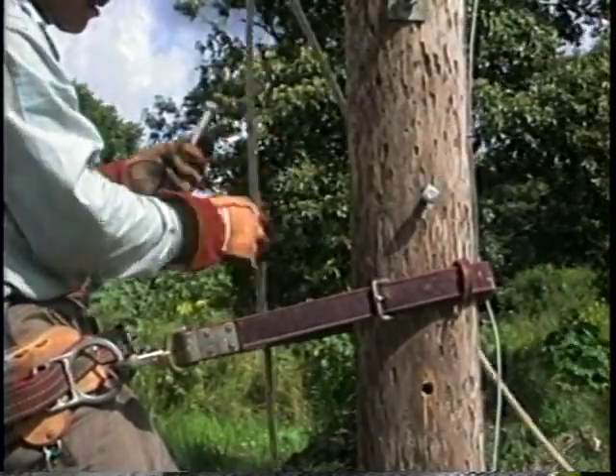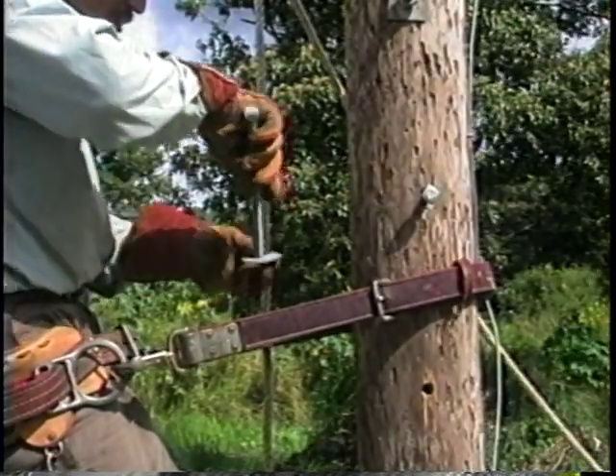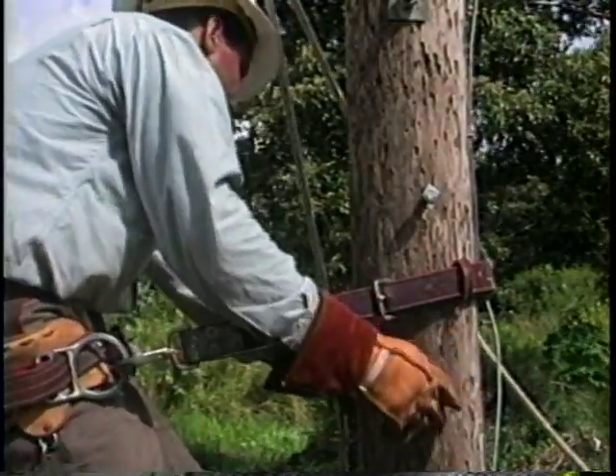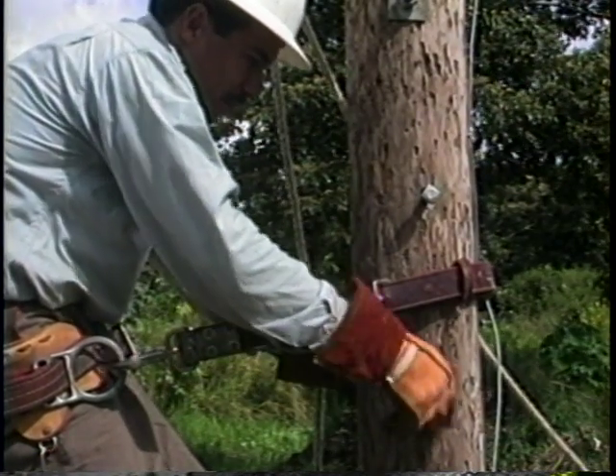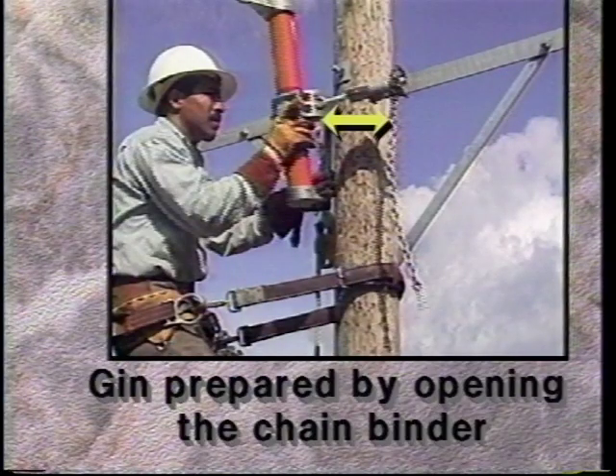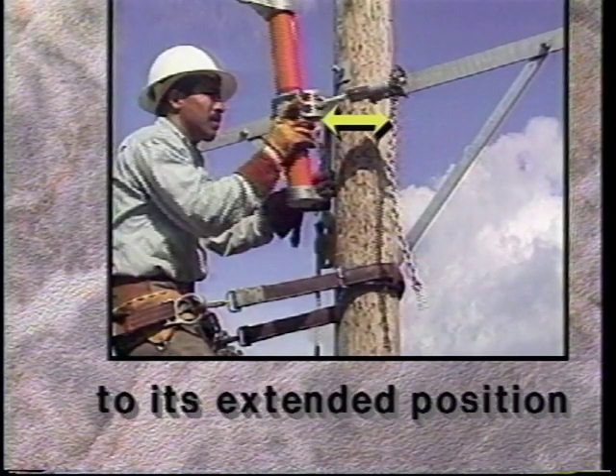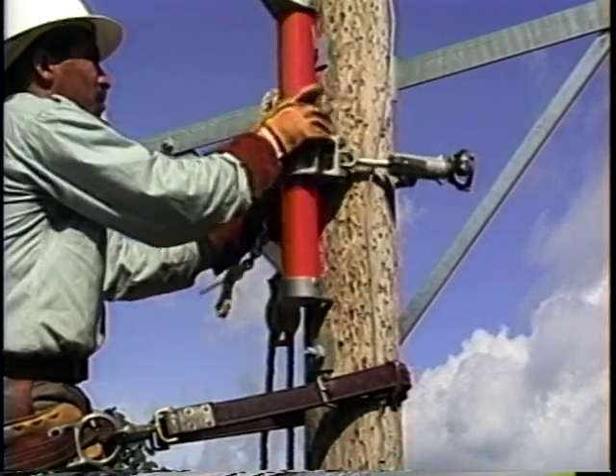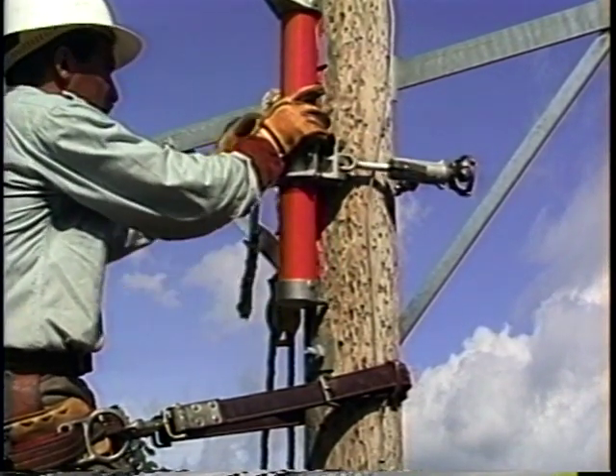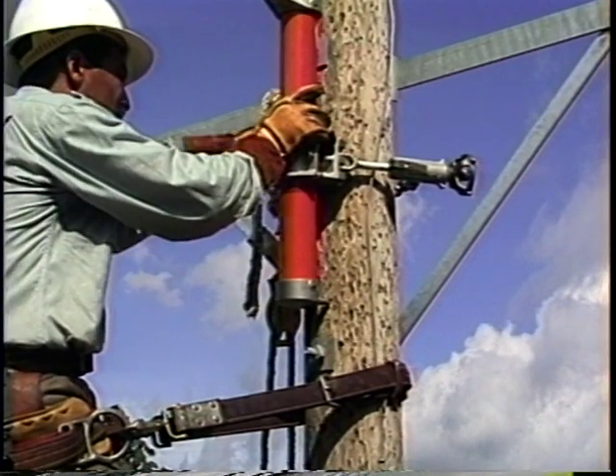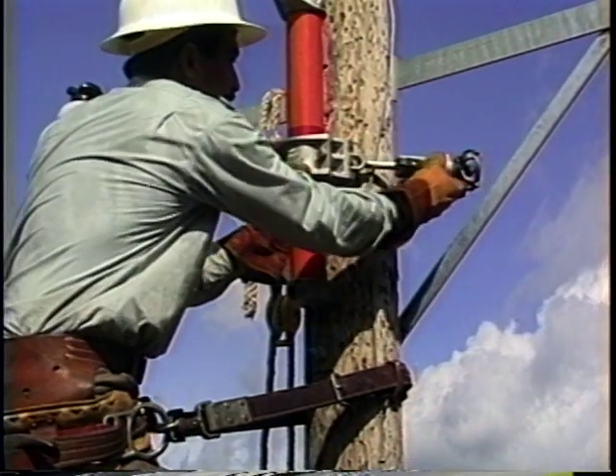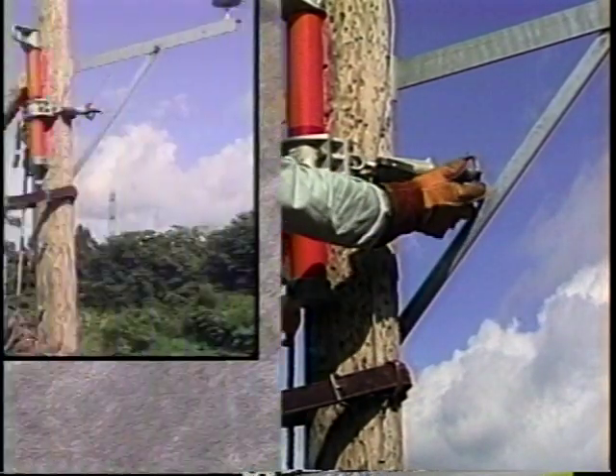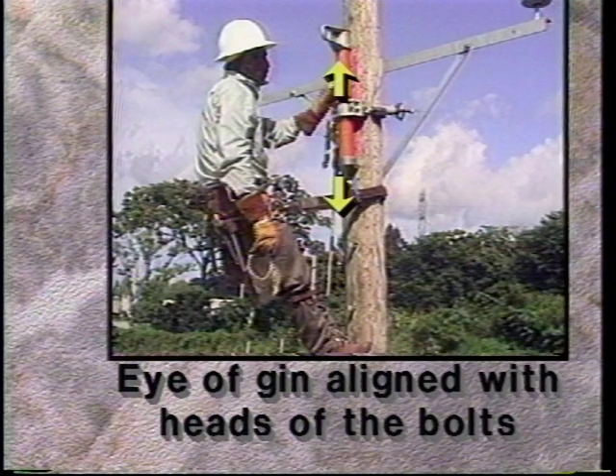Structure preparation. The position where the transformer will be is located, and holes are drilled if required. Machine bolts are inserted, with the heads placed on the side of the pole where the transformer hanger brackets will be located. The transformer gin is prepared by opening the chain binder to its extended position and then raised to the lineman. Once received, the transformer gin is installed. It should be positioned high enough on the pole to allow the transformer to be raised with the block and tackle. The eye of the gin should be aligned with the heads of the bolts to facilitate easier transformer mounting.